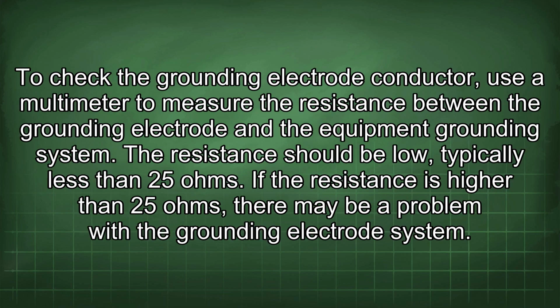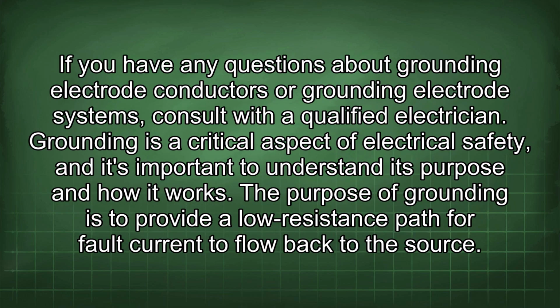To check the grounding electrode conductor, use a multimeter to measure the resistance between the grounding electrode and the equipment grounding system. The resistance should be low, typically less than 25 ohms. If the resistance is higher than 25 ohms, there may be a problem with the grounding electrode system. If you have any questions about grounding electrode conductors or grounding electrode systems, consult with a qualified electrician.